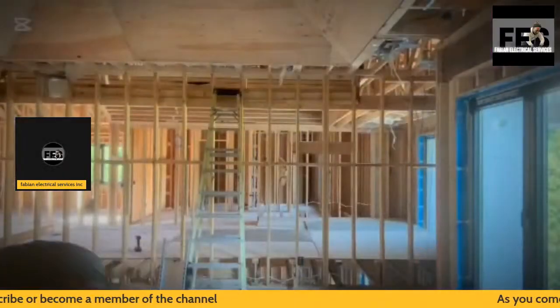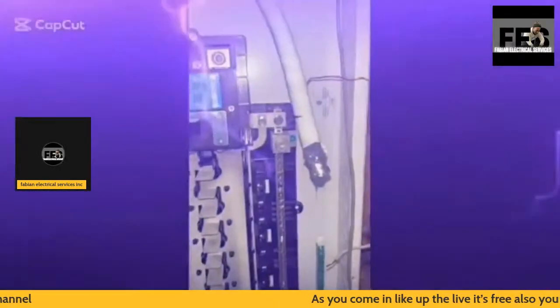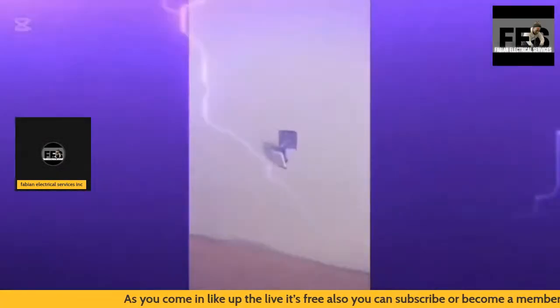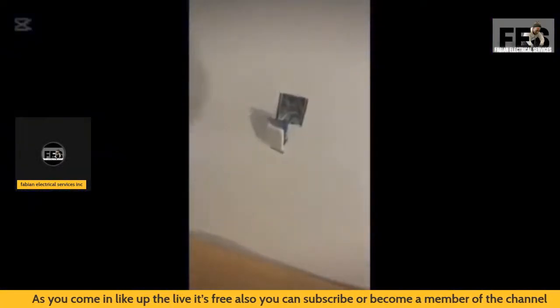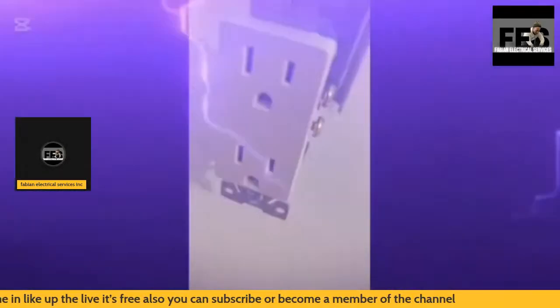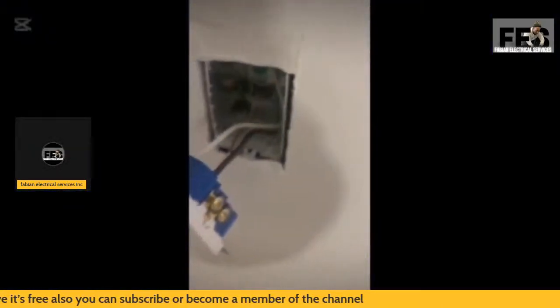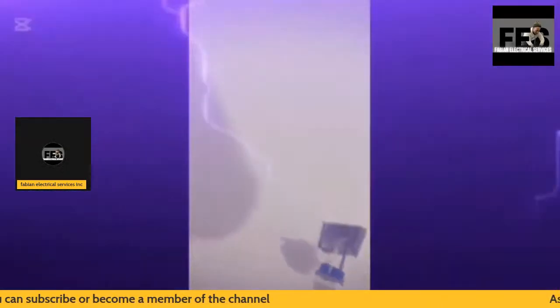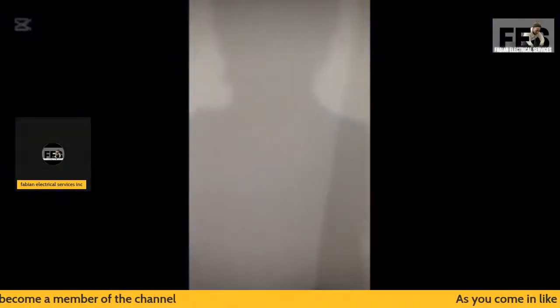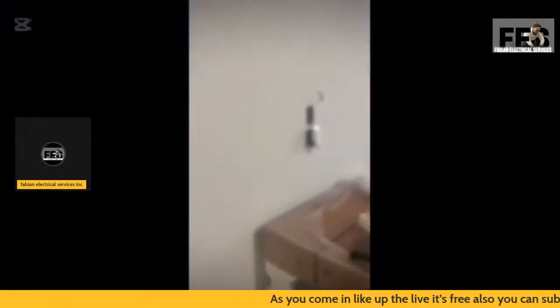So again, sometimes when there's a disconnect involved, it's going to go directly into the disconnect, and depending on what system you're dealing with when it comes to grounding - if it's a Teck cable, then you don't need to continue that grounding. If it's not, then you have to bring it over.